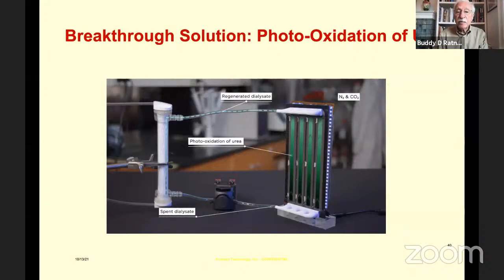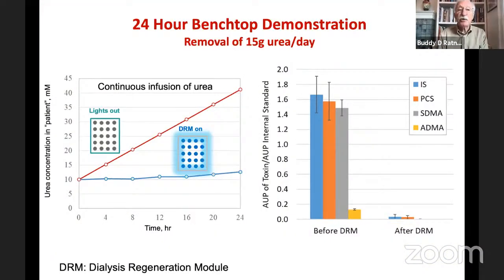So this sort of artist's illustration shows really what's going on. Off to the left is the patient. The patient's blood is going through that hollow fiber dialyzer. The dialysate comes in. It picks up the urea from the blood. It goes into the photooxidation unit, which you see on the right, is passed over the catalyst in the presence of UV light, and the urea goes off as nitrogen and CO2, and then that dialysate can go back into the hollow fiber dialyzer and pick up more urea. So that's the system we envision.